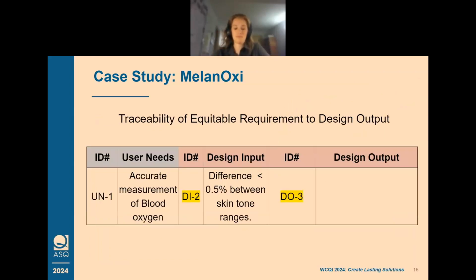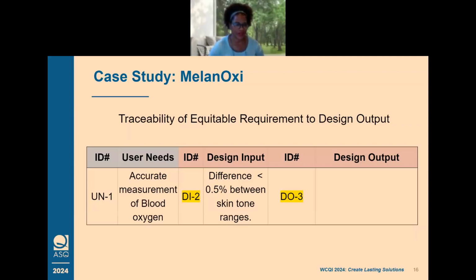Now that we have that equitable requirement example, we're going to need a design output. The design input is that high level requirement, and now a design output will get translated to an actual specification that needs to be reviewed and approved by your team. Because as you know, design outputs could be specifications, they could be drawings, they could be work instructions. It's basically the preliminary recipe for your design builds to be built against. So it's basically a bunch of requirements that have been translated into formal and approved documents in your quality management system.